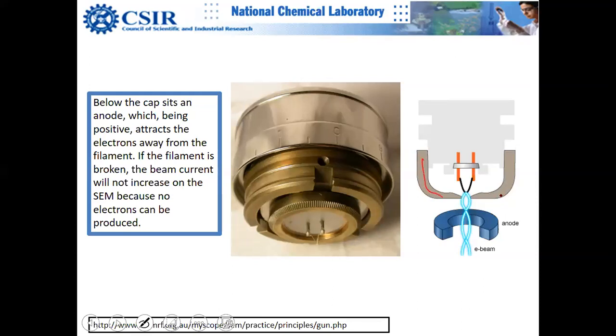The Wehnelt cap is negatively charged. Electrons when ejected go in all directions. When you apply a negative bias, they are repelled and collimate to a point. Basically they form a crossover point. After that you apply a positive anode voltage to accelerate them.